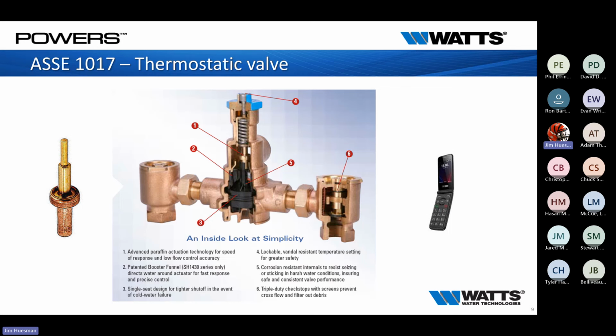So we'll run into buildings where it's been working well for years, but about two years in, we notice we get a real hot glug or a real cold glug and we're all over the map. What you'll find is, because we're only working with expansion and contraction using pieces that are stable and set inside a valve, there's no way for that buildup to shake off on its own. You have to physically rebuild this thing.